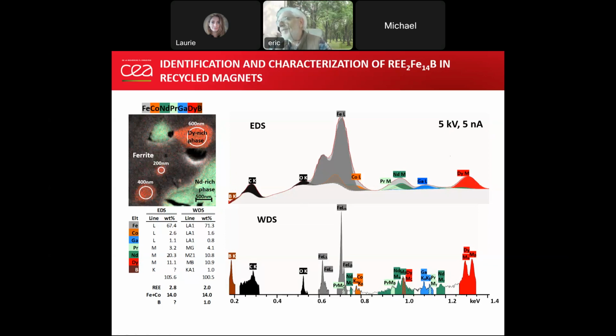small beam current for this analysis. And the last point is that now we're particularly sensitive for the detection of boron. So here you can compare the result obtained with WDS with that obtained with EDS. And so now we obtain the correct stoichiometry, which is indeed the 2-14-1 phase, which is present here.